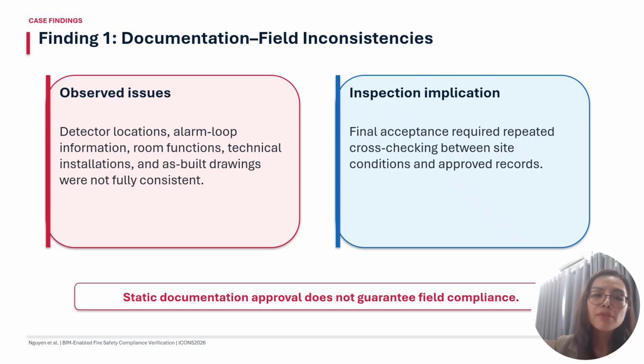Finding one: documentation-field inconsistencies. The issue observed is that detector locations, alarm loop information, room functions, technical installations, and as-built drawings were not fully consistent. The inspection implication: the final assessment required repeated cross-checking between site conditions and approved records. Documentation approval does not guarantee field compliance.